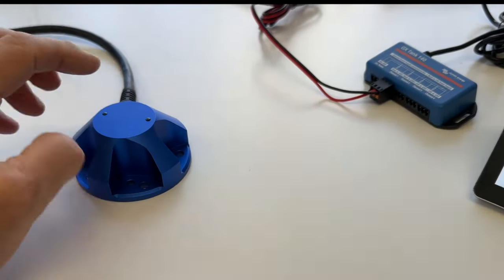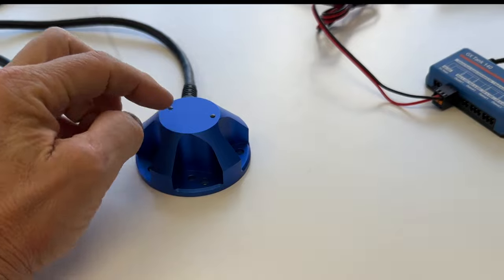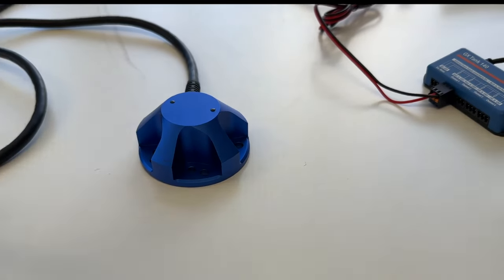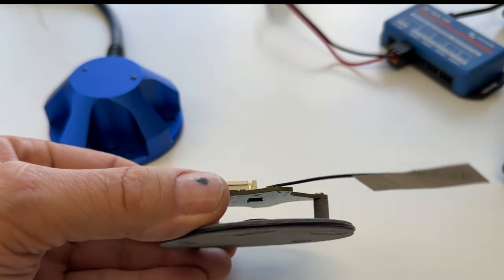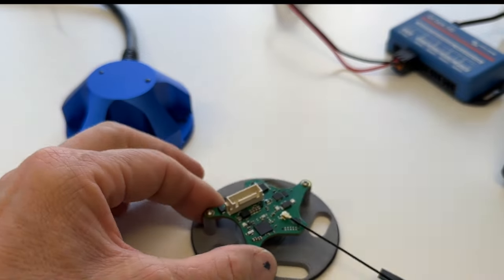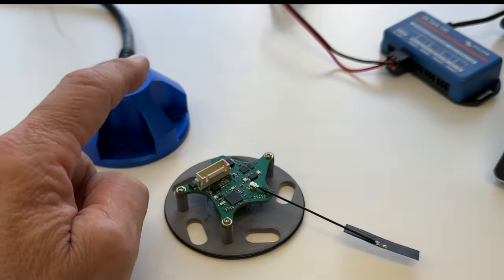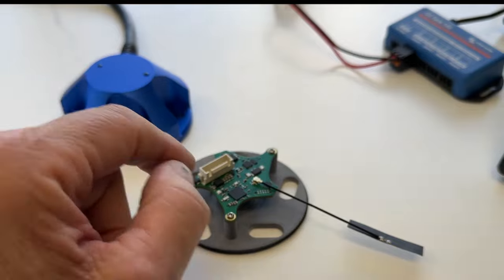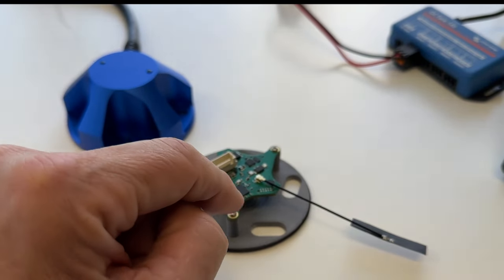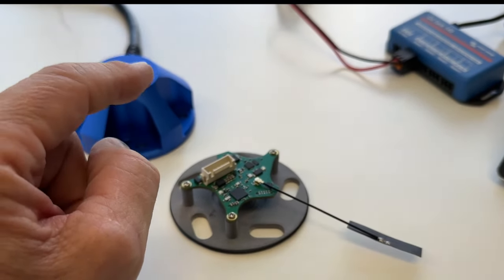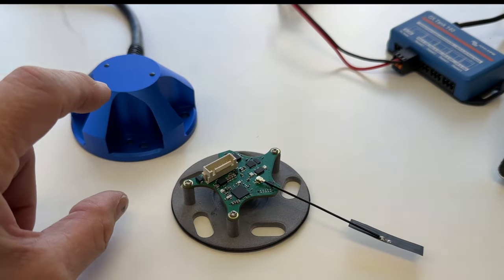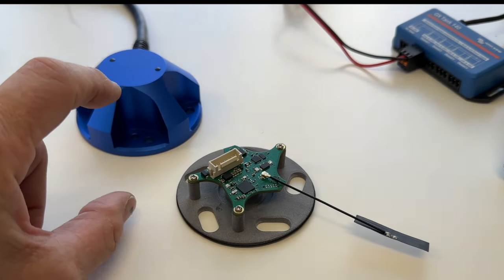Now, the phase coherent tank radar is a very small radar chip. So now we're going to go to the board. You can see it underneath there. It can't have any other components on that side. It's got an accuracy of 2.5 millimeters, and we have this set up from 0 to 2000 millimeters in depth. It does have a dead band. So the dead band's about 40 millimeters on the top of the tank, but that's okay.